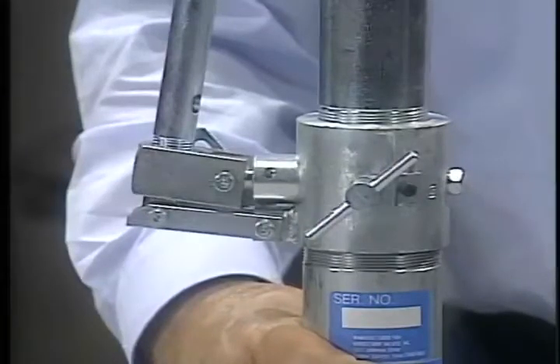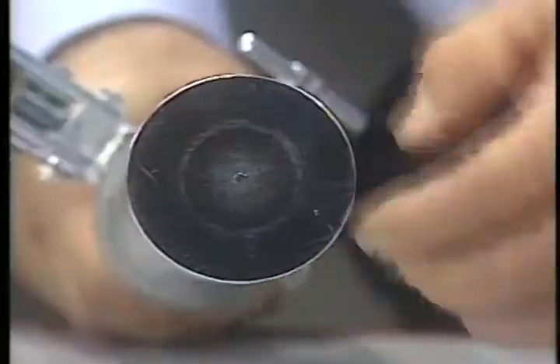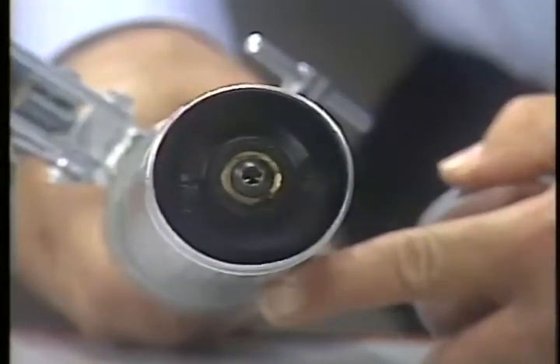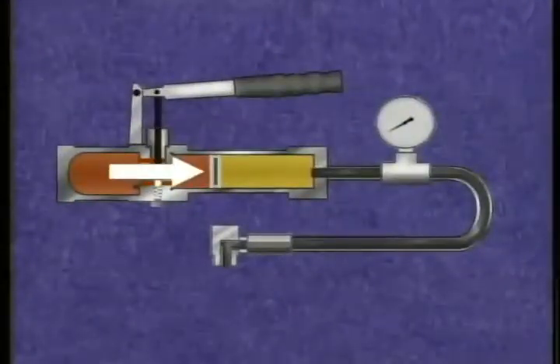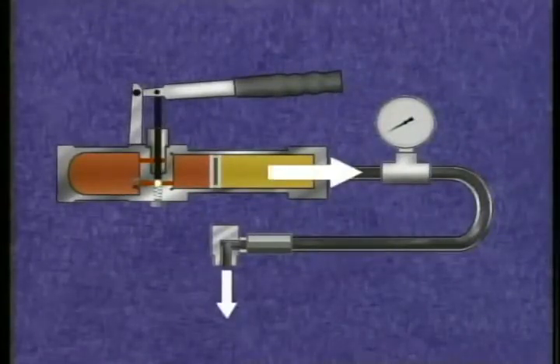The gun handle is attached to the piston of an internal hydraulic pump and operates the pump. A bag in a cylindrical barrel attached to the gun body serves as a reservoir for the hydraulic fluid. The pump mechanism generates hydraulic pressure that is applied to an internal floating piston. The floating piston pushes against the sealant, forcing it through the hose and button head coupler into the valve.